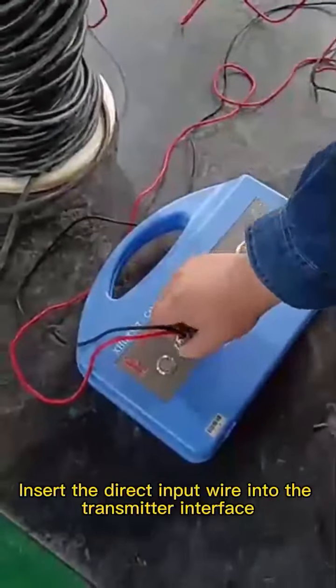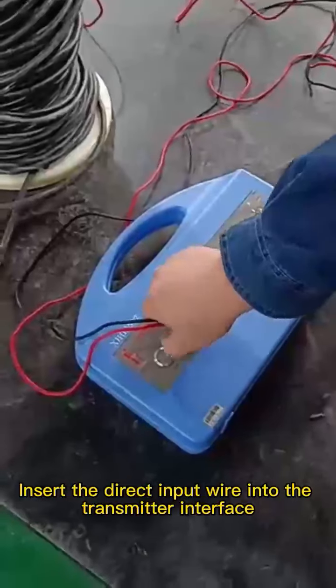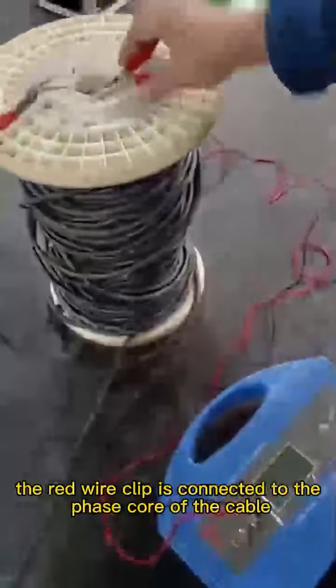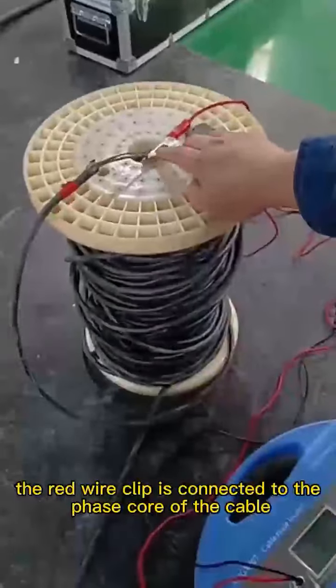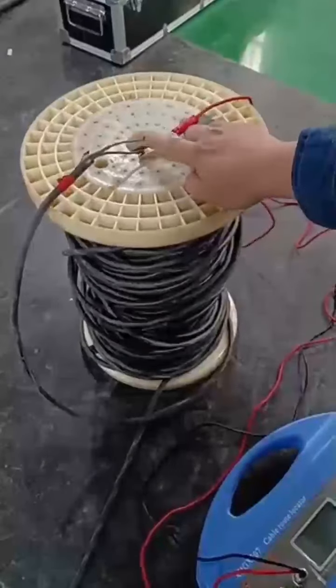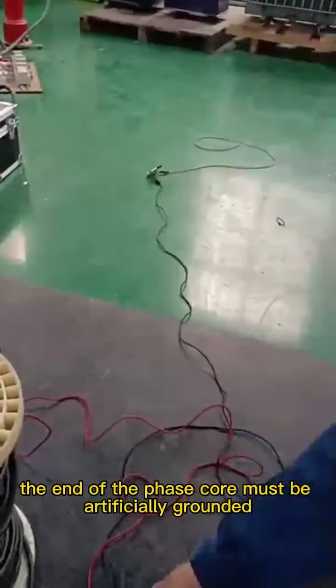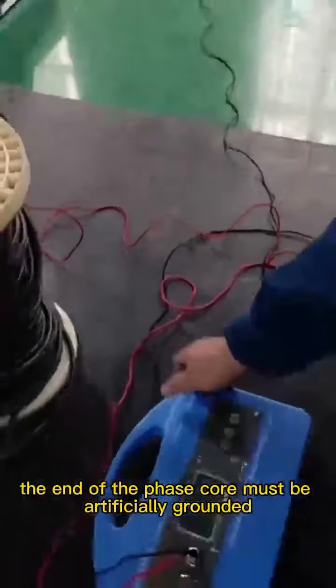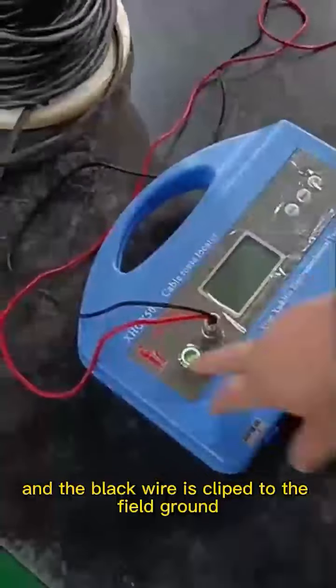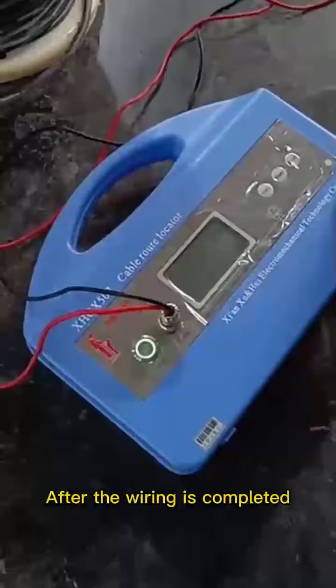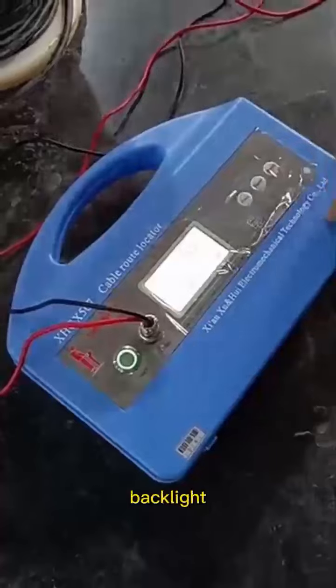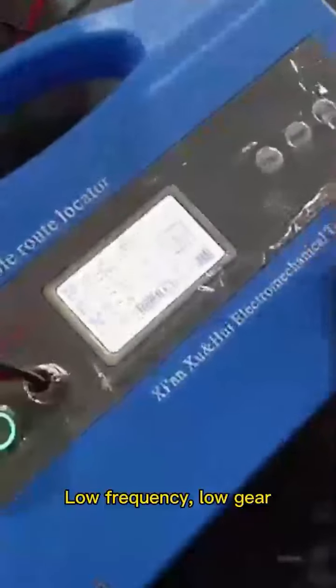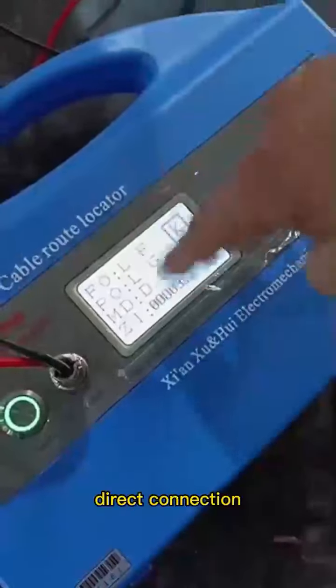Insert the direct input wire into the transmitter interface. The red wire clip is connected to the phase core of the cable. The end of the phase core must be artificially grounded, and the black wire is clipped to the field ground. After the wiring is completed, power on, backlight, low frequency, low gear, direct connection.